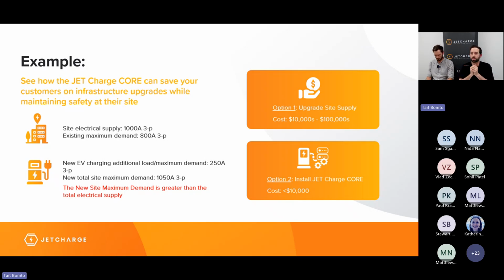Often it costs more than $100,000. We see timeframes for this blow out to more than 12 months, even up to 24 months, to get that new supply. And so using the JetCharge Core presents an alternative to that. By installing the JetCharge Core load management system, you can control that EV charging load, that new 250 amps of load, within the existing 1000 amp three-phase electrical supply. This means that the building owner can reduce their infrastructure costs. They have a higher chance of the project going ahead if they don't have to upgrade their site supply, and it means you as well can get started on the project immediately.